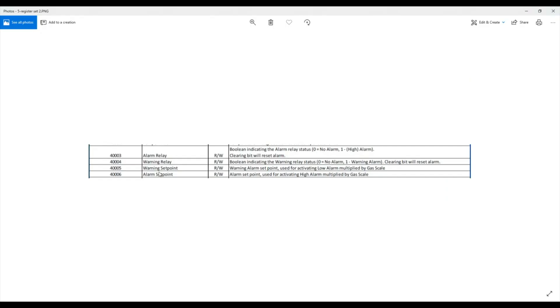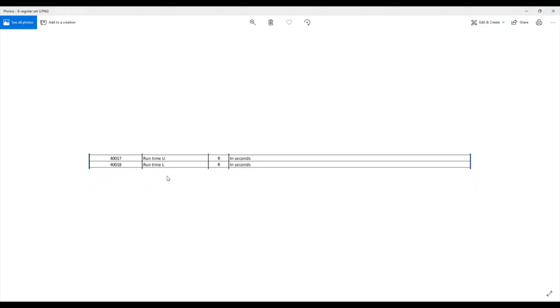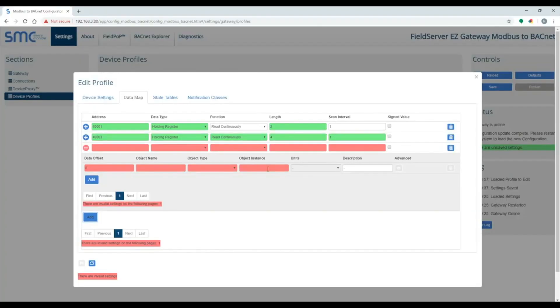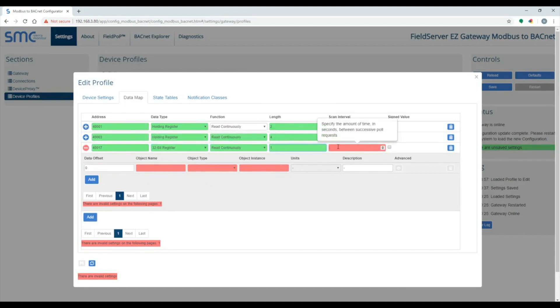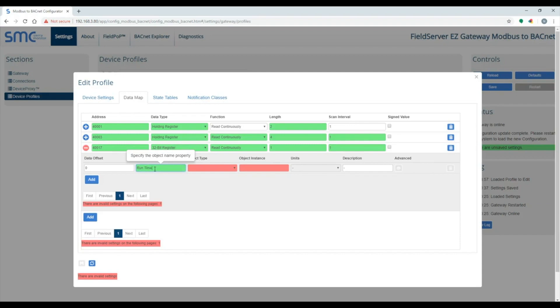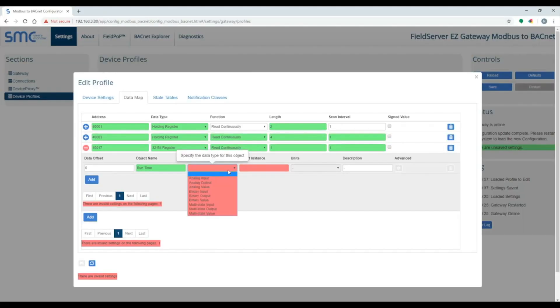The next point is a 32-bit register split across two 16-bit registers. You need to use a data type of 32-bit reg with a length of 1, and that will automatically combine the two 16-bit integers into a 32-bit integer.